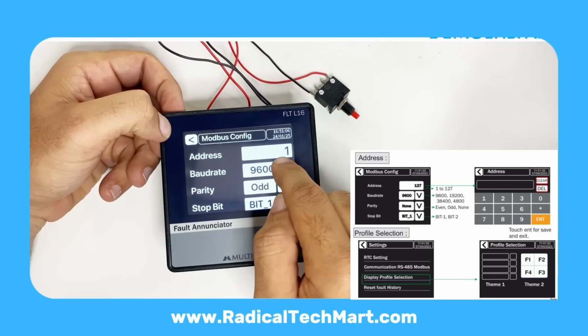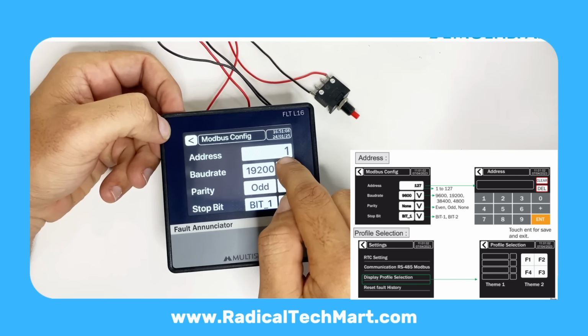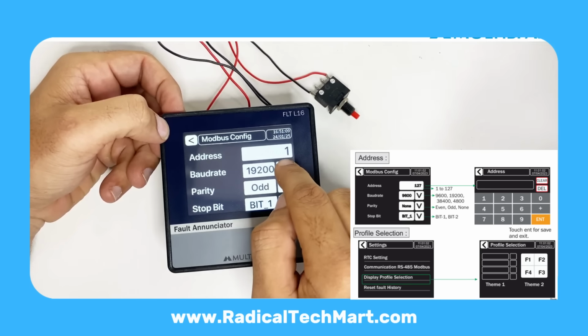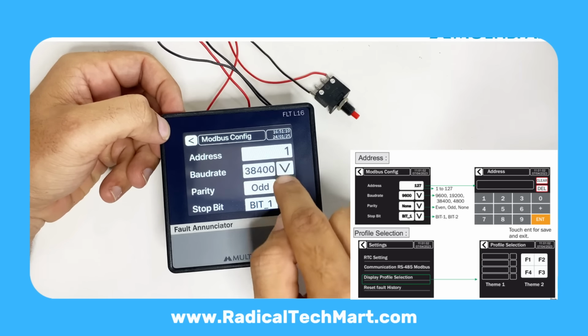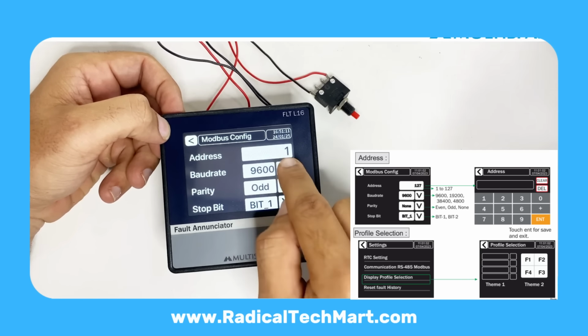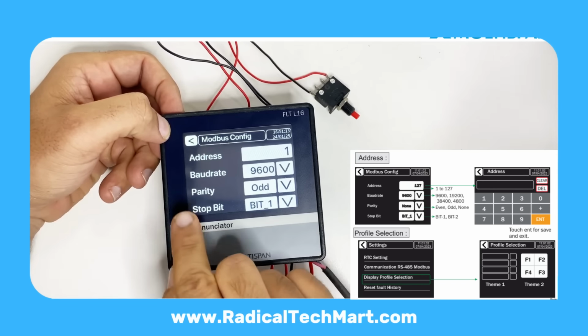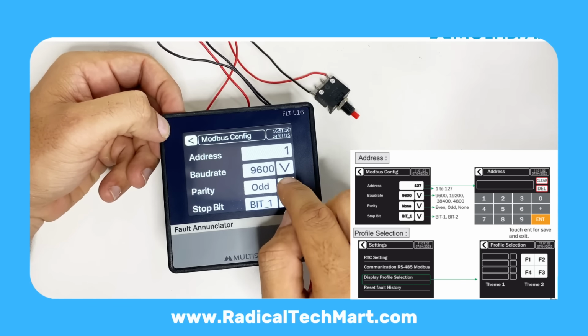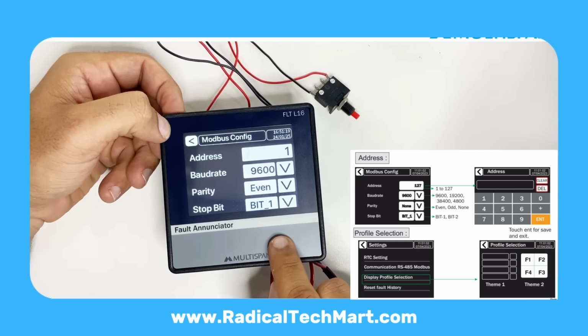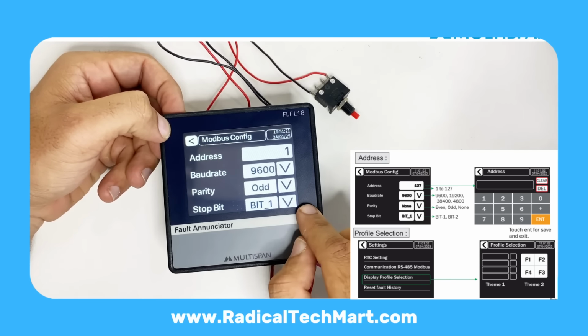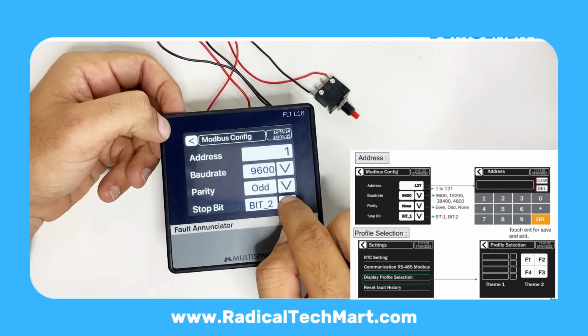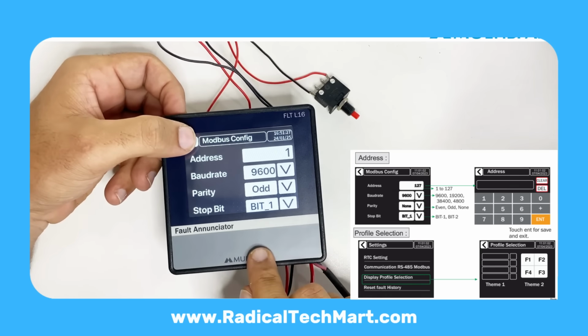Modbus address 1 to 127. Baud rate 9600, 19200, 38400. Parity, odd, none, or even. Stop bits 1 or 2. These settings must match your PLC, BMS, SCADA configuration for communication to work.